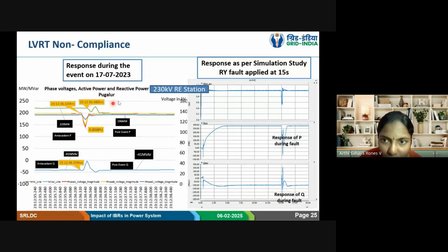We have the PSCAD model of the system, but when we study in the simulation, we are seeing proper response, like it is coming back. You can see at PPC, the megawatt before and after are both the same. This is VPPC. The same dip in the voltage was applied. So at grid end, this is the dip.